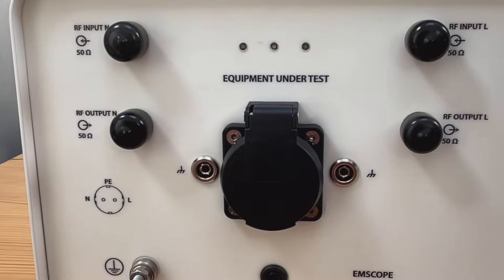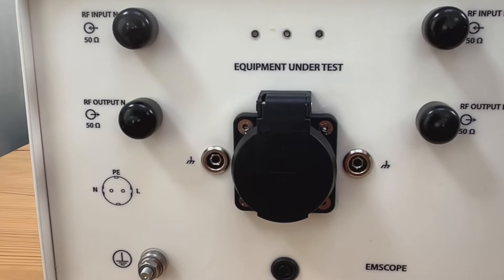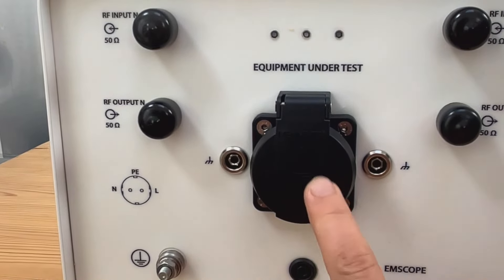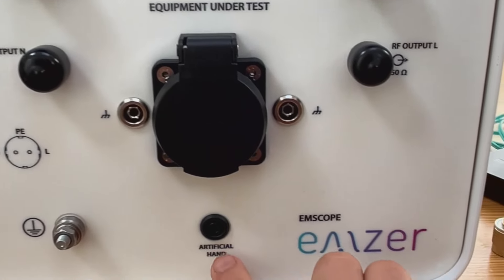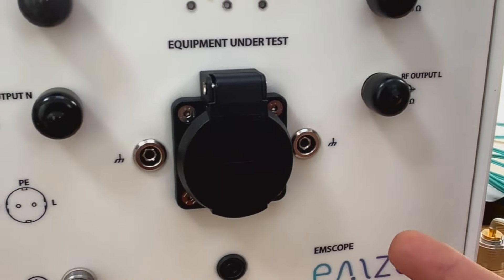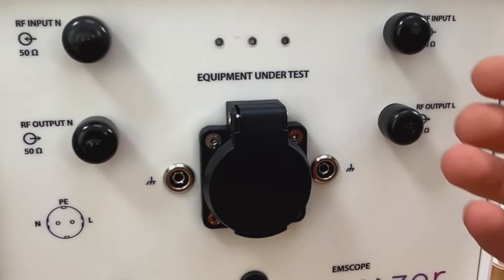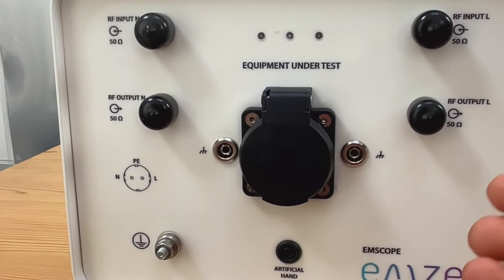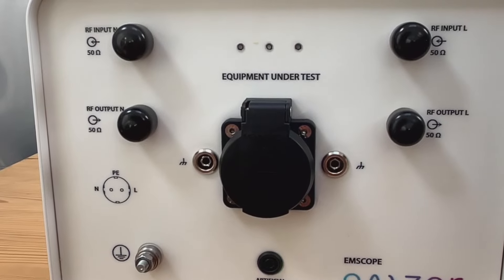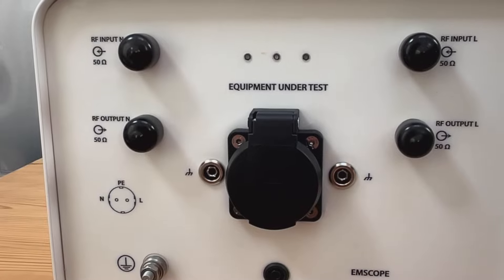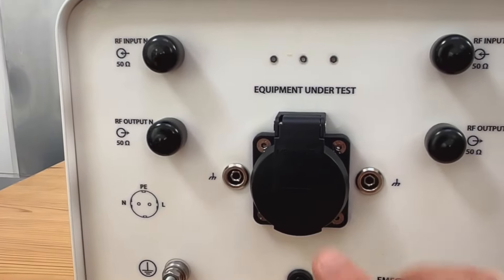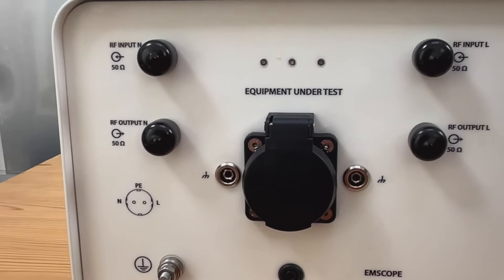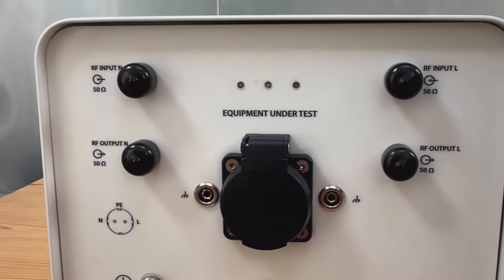Of course, the standard DUT connection here, earthing connection here and here. Also here you can see the artificial hand. This is for products such as a hand tool that is mains powered, where in a typical use scenario you would hold the hand tool. The EMC test tries to simulate that kind of scenario. Hence there's an artificial hand connection. Normally you connect the cable to the artificial hand and you have a tinfoil wrapped around your product for such test.